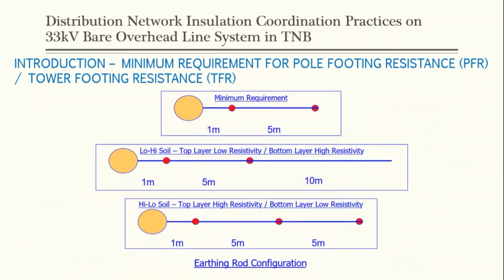All right. So the minimum requirement for earthing is as shown on the screen. Okay. For example, if you have a homogeneous soil, the minimum requirement is this, considered from the helicopter view. You have the pole, and this is the first rod, 1 meter away from the pole, and another copper rod with the counterpoise earth tape at 5 meter apart.